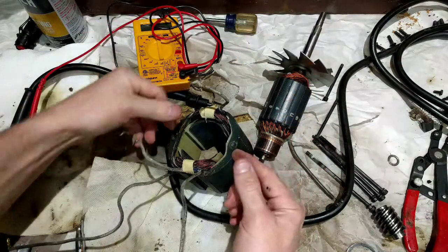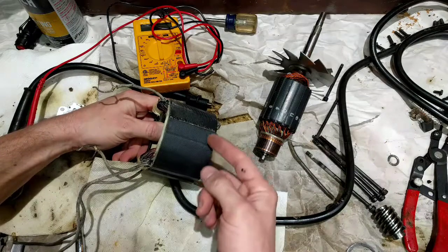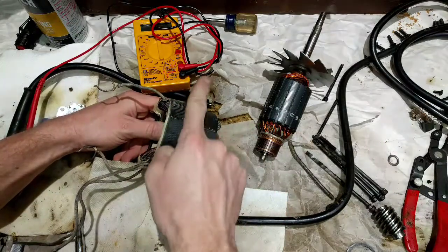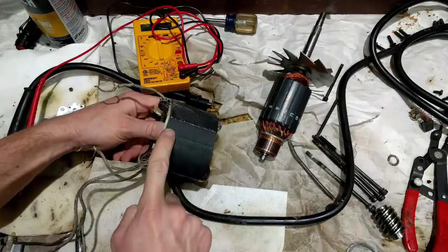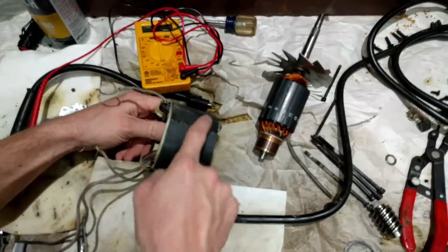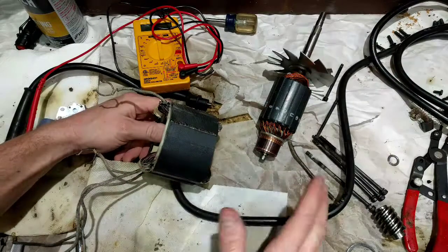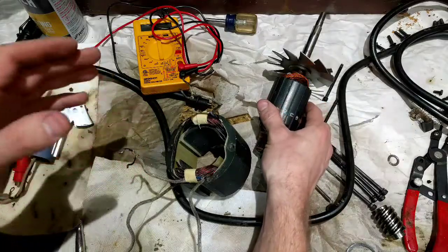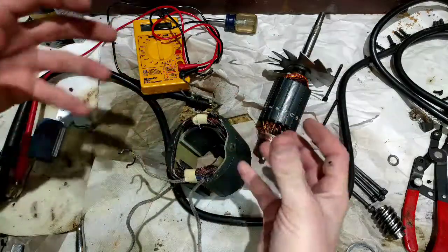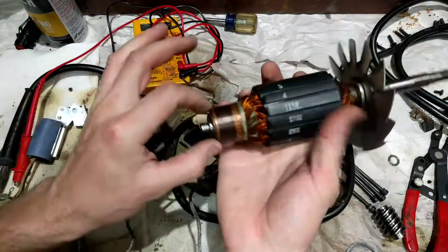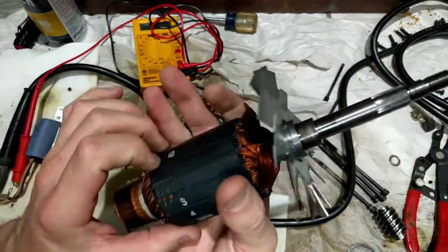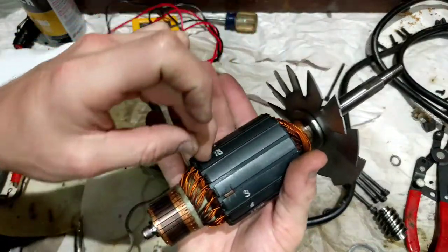But if these were continuous, solid, you get what they call eddy currents. Every time that changes direction, you've got a flow, and instead of just flowing through thin plates, it's now able to go in other directions, electrons bouncing off of each other. It's like electron pinball. Not good. It generates heat. If you can think of friction, resistance, these things bouncing around in there, heat, collisions. Same theory over here. Same striations, same construction of stacked metal plates.